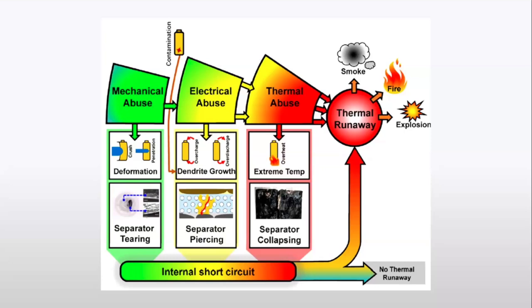Any source of fire near such a battery - even a house fire caused by the reticulate system failing - if lithium batteries are in close vicinity, and they're normally placed near a distribution board or a lot of wiring, then even an external fire starting in a home can result in ignition of your lithium battery bank.